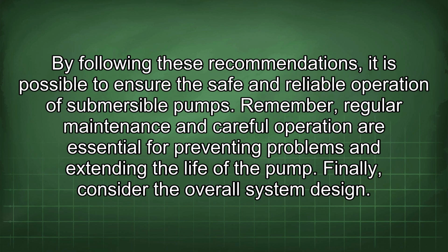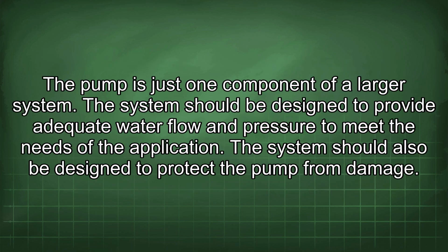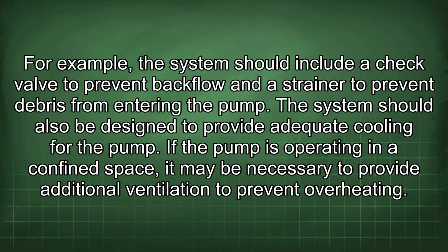Finally, consider the overall system design. The pump is just one component of a larger system. The system should be designed to provide adequate water flow and pressure to meet the needs of the application. The system should also be designed to protect the pump from damage. For example, the system should include a check valve to prevent backflow and a strainer to prevent debris from entering the pump. The system should also be designed to provide adequate cooling for the pump. If the pump is operating in a confined space, it may be necessary to provide additional ventilation to prevent overheating.